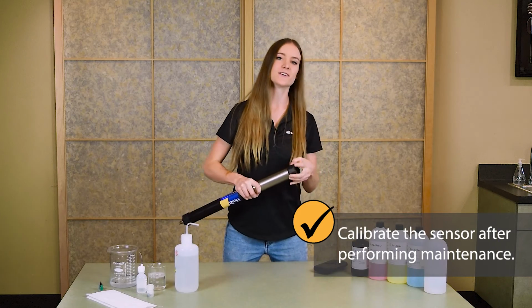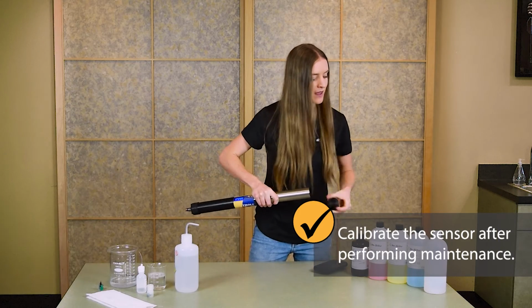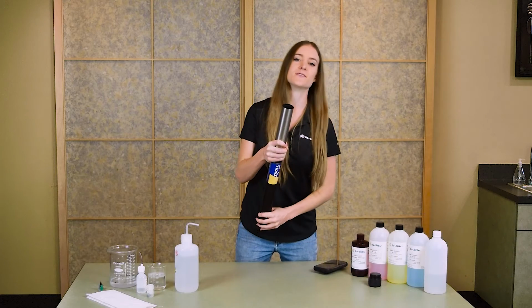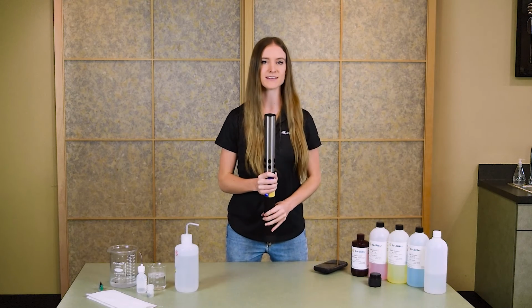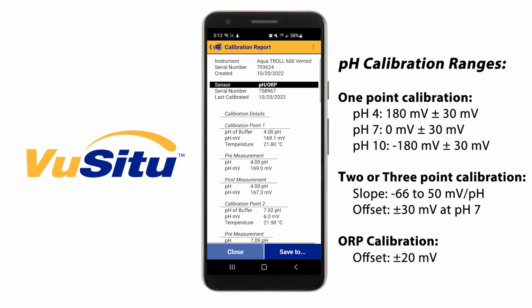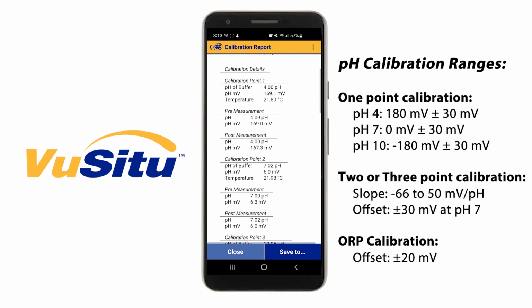Always make sure to calibrate your sensor after performing maintenance. I'll include a link in the video description if you need a refresher on the calibration process. After calibration, check the calibration report to make sure that the pH millivolt values are inside of the acceptable ranges.